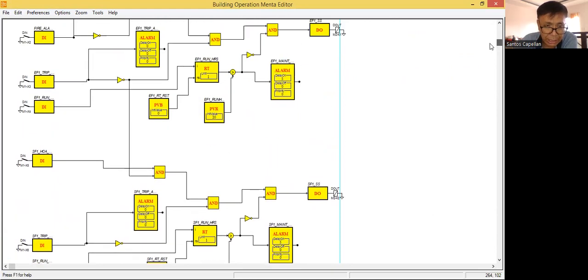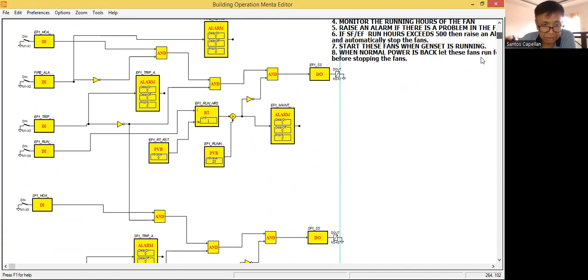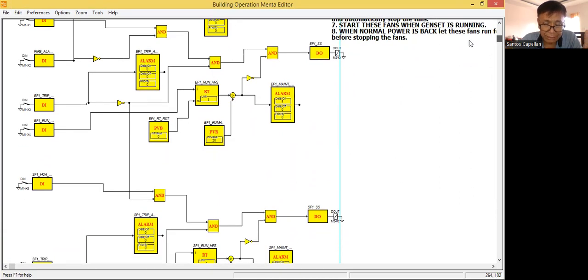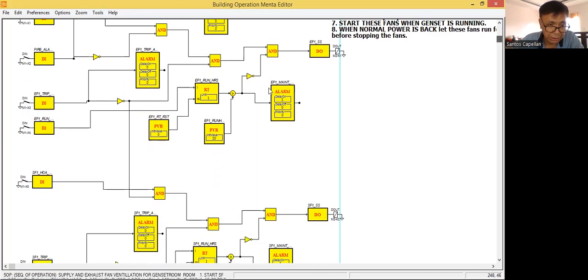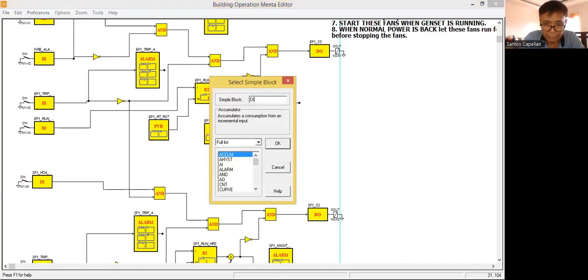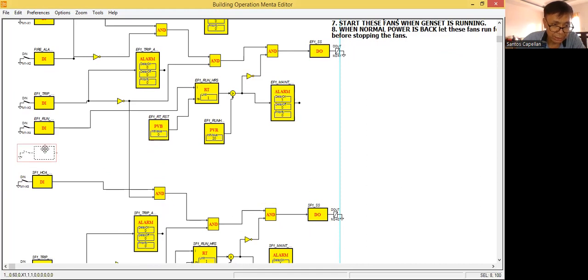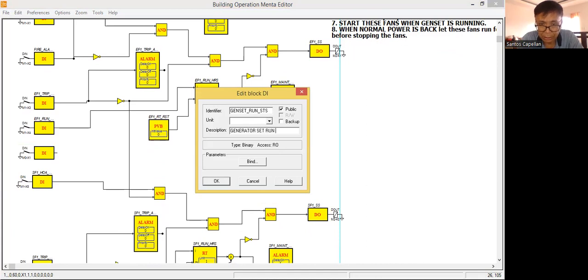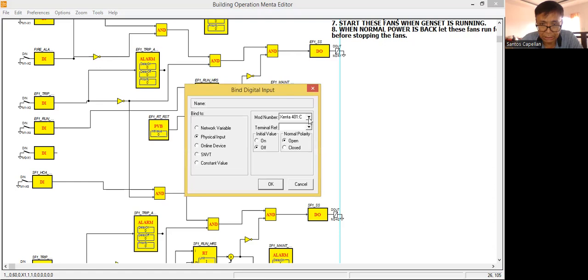So that will be my new logic for the new system — supply and exhaust fan ventilation for a generator set room. Now, start these fans when the generator set is running. Apart from being in automatic with no trip on each fan, we have to run this only when the generator is running. So I need another input here — I will specify a simple block DI, and I will name this one as genset run status.